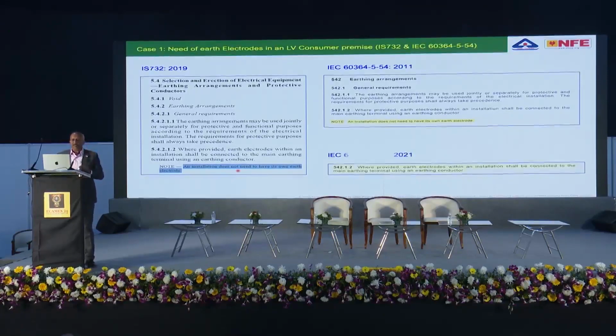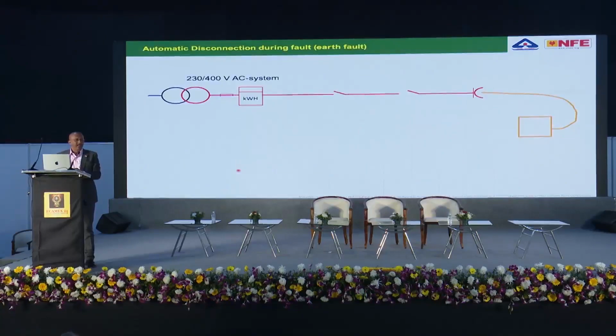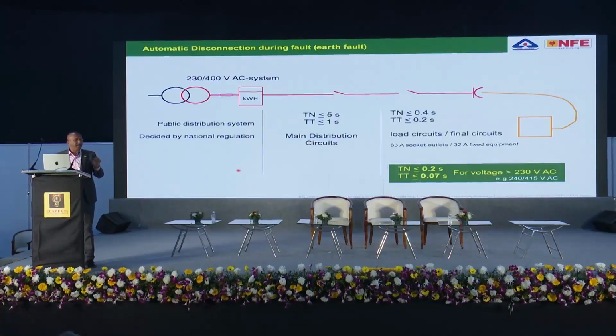The protection for safety, or protection against shock, the fault protection, we say is fault protection by protective equipotential bonding and automatic disconnection of supply. Automatic disconnection means the protective device should trip within a certain time. It is not like your MCB can trip after a few seconds. No. For example, on the final circuit, in a TN system, within 0.4 second, 400 milliseconds, the protective device should trip. In case of a TT system, within 0.2 second, 200 milliseconds, the device should trip. And if the device trips within this time, there is no fire, there is no shock.